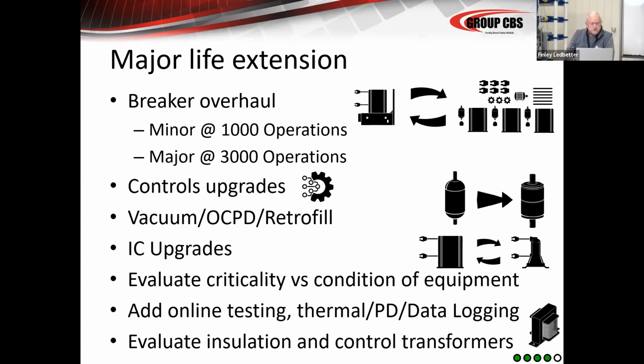Okay, so we do get into our major life inspection and major life extension situation here, where minor overhauls at about 1,000 operations, major overhauls at about 3,000 operations on the mechanism. And there again, we're talking about medium voltage vacuum breakers, medium voltage meaning 1,000 volts to 38,000 volts, mostly draw out breakers. So at the 3,000 operations, we'd like to see a major overhaul of the breakers. At 1,000 operations, we'd like to see some minor overhaul.